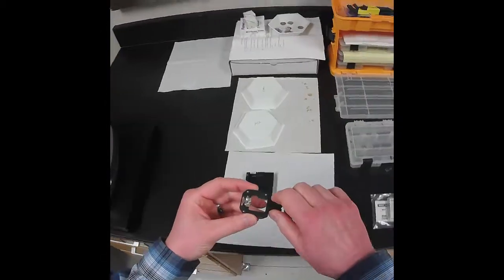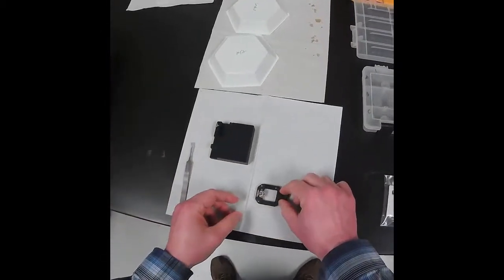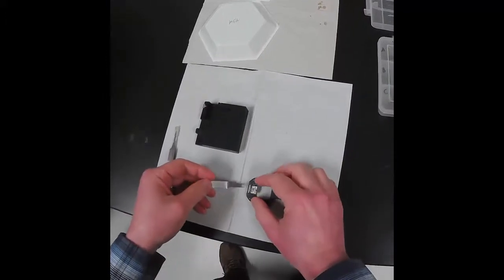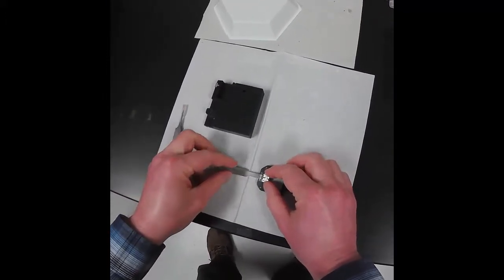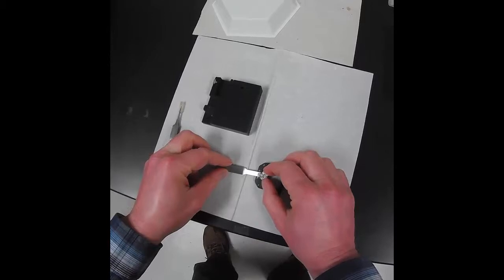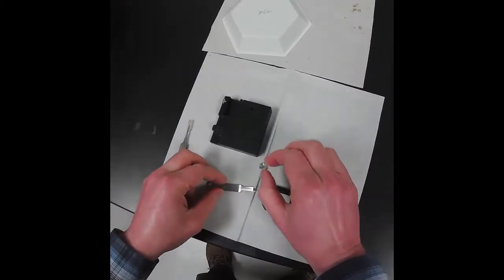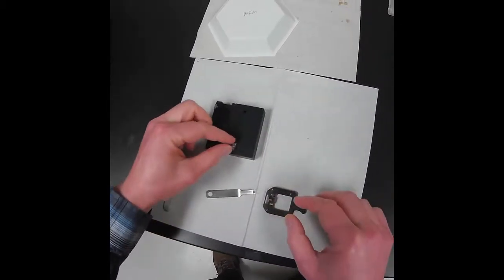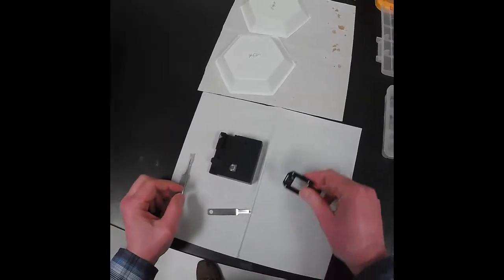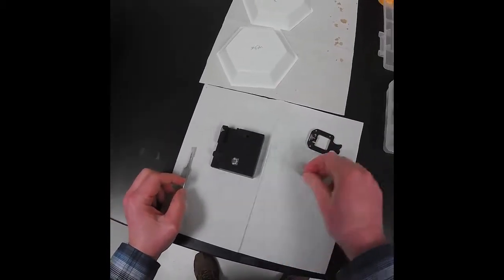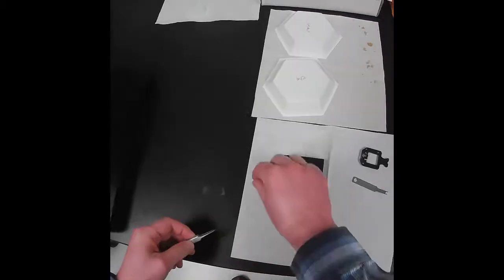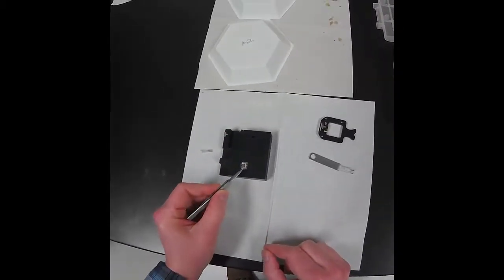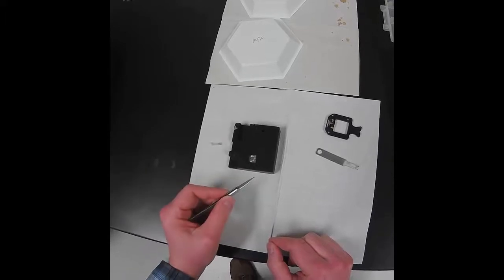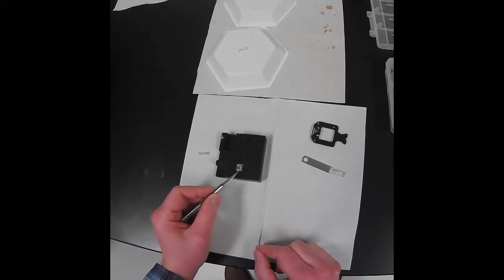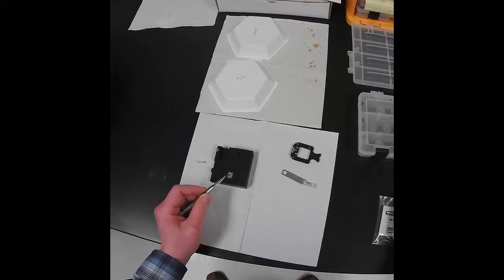Now notice in the cartridge we have the chip carrier, and if we need to, we can remove it using this crowbar to lift up on this spring, remove the chip carrier. If your tip breaks, Bruker no longer makes pre-mounted chips, so you'll have to change the chip out of the chip carrier. And this tool, this jig, is used for that. It's very tricky. You need a lot of practice, so ask your instructor to help you with that.